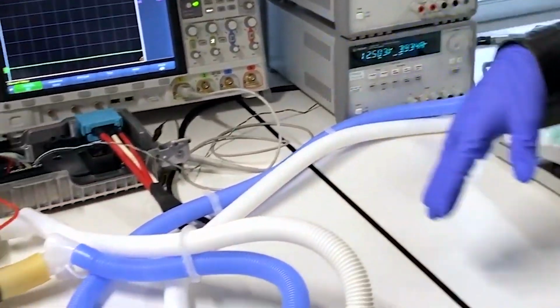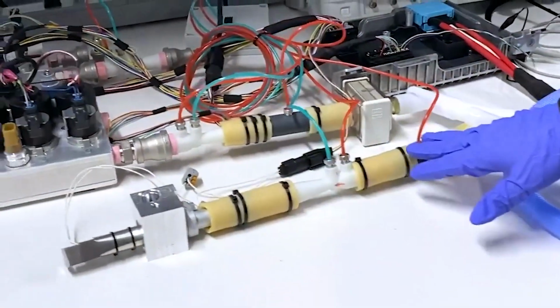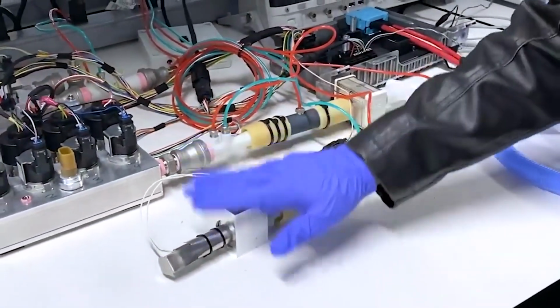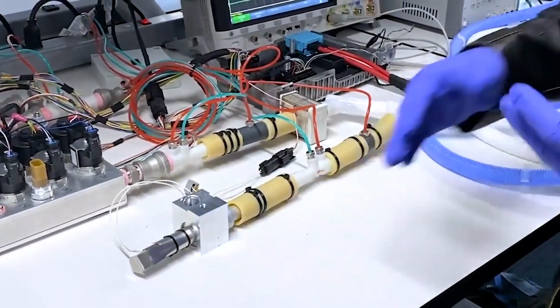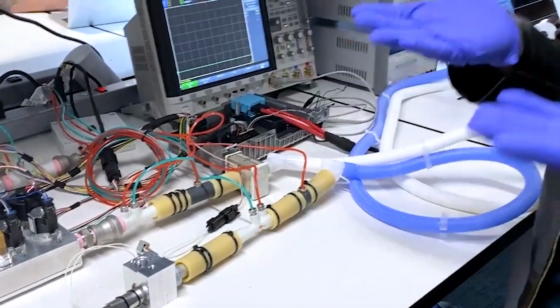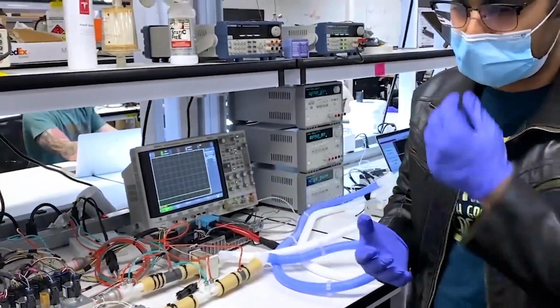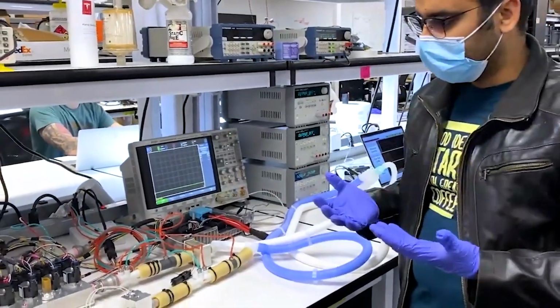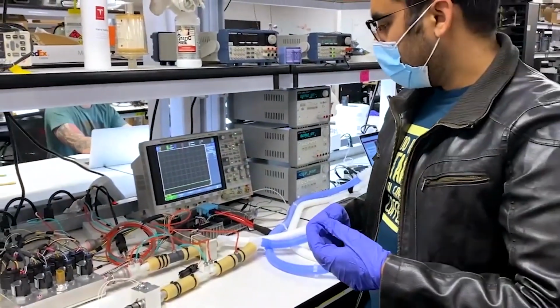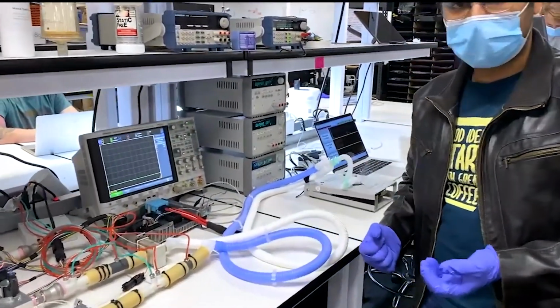air and then goes through the exhale pipes and goes through a set of sensors, and then goes through the exhale valve, which is used to throttle the pressure of the lung, so you always keep a positive pressure on the lung, which helps the COVID-19 patients to breathe, keeps their lungs open. So yeah, that's the Tesla ventilator first prototype.